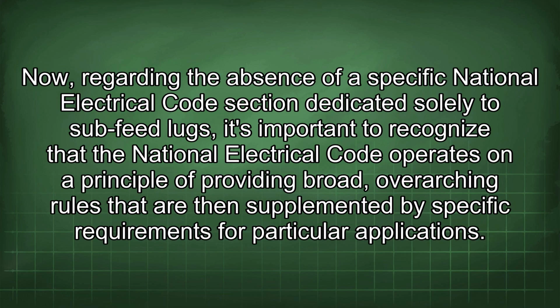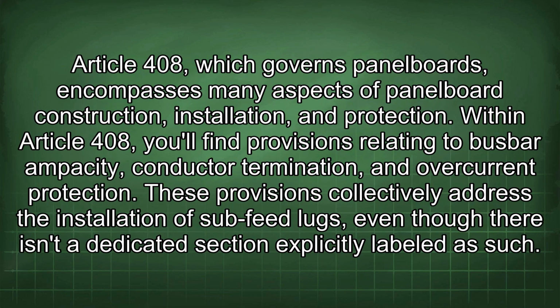Now, regarding the absence of a specific National Electrical Code section dedicated solely to sub-feed lugs, it's important to recognize that the National Electrical Code operates on a principle of providing broad, overarching rules that are then supplemented by specific requirements for particular applications. Article 408, which governs panel boards, encompasses many aspects of panel board construction, installation, and protection. Within Article 408, you'll find provisions relating to busbar ampacity, conductor termination, and overcurrent protection. These provisions collectively address the installation of sub-feed lugs, even though there isn't a dedicated section explicitly labeled as such.